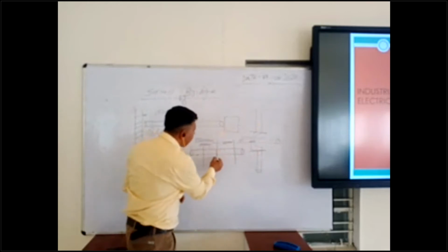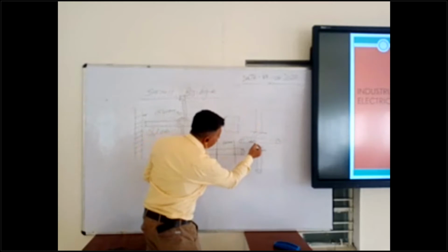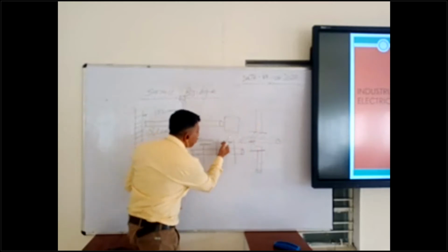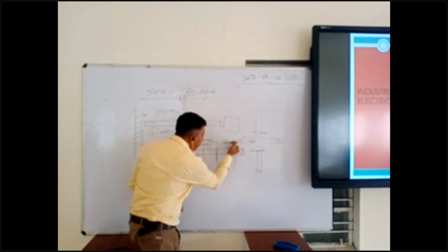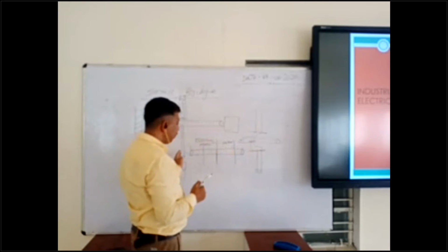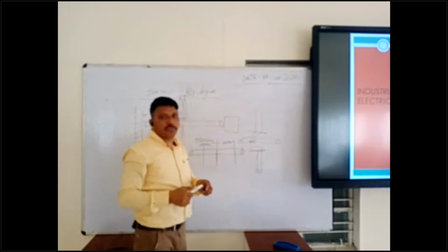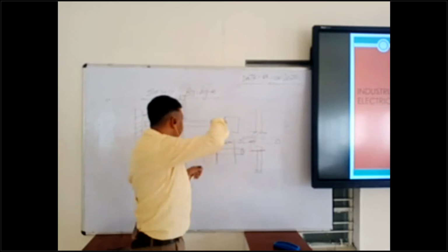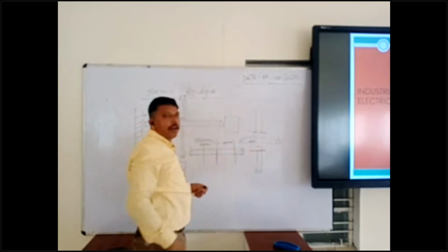This is the center point, the crossing place of the pipe. You can mark it here. Then, from here, mark 100 mm or 10 centimeters on one side and 10 centimeters on the other side for bending purposes. We can bend with a GI pipe bender.